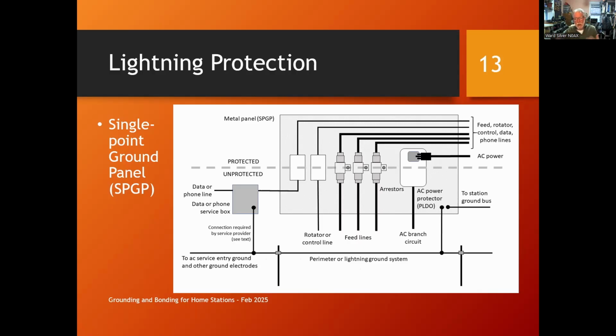Now, if you've got a concrete driveway or something, you can't bust up the driveway to run it through there. So you might make an open ring and skip the driveway or the patio. That's common. The idea is just to get a lot of wire and ground rods in the earth to provide this big, heavy, direct path to the earth for the charge to dissipate. Each one of these services, when you have the technician come, they are required to establish a ground connection. They will look for your home ground connection, and if they can mount everything over there by the service panel, they will. If they can't, they will drive in their own ground rod.